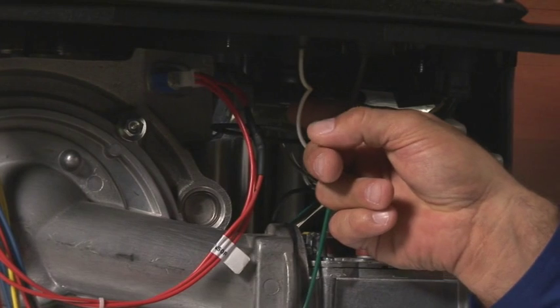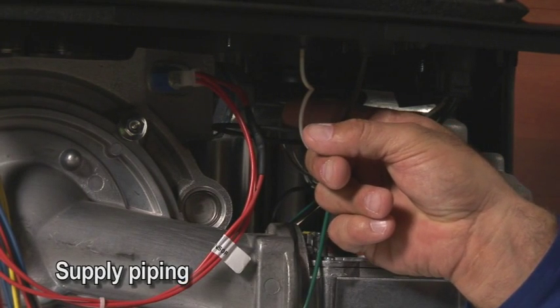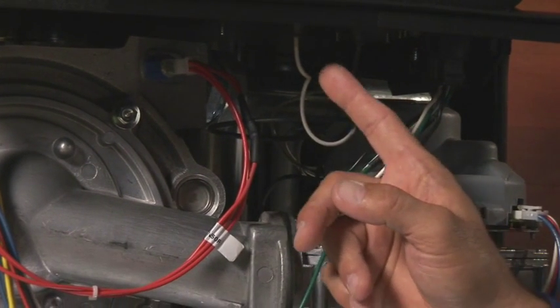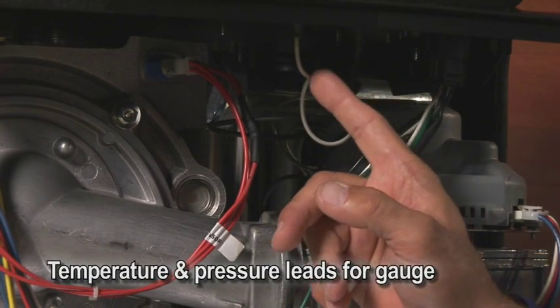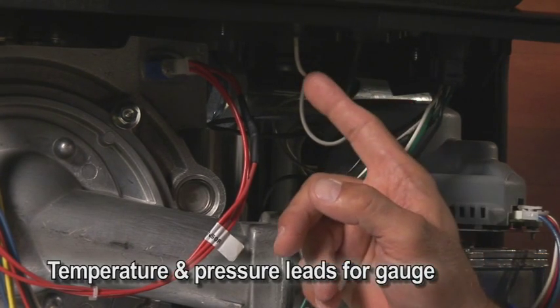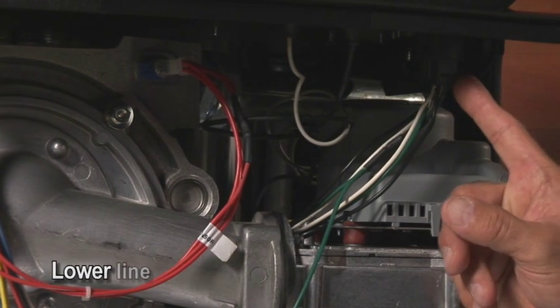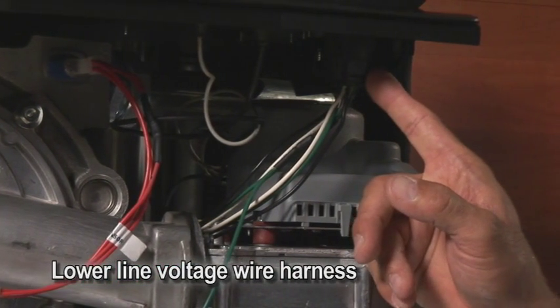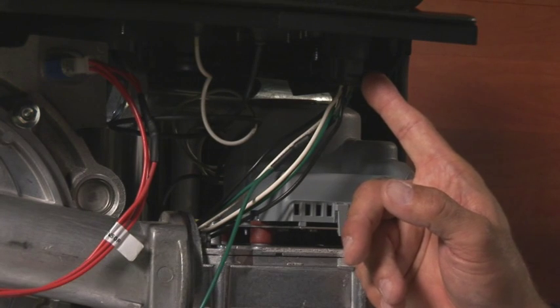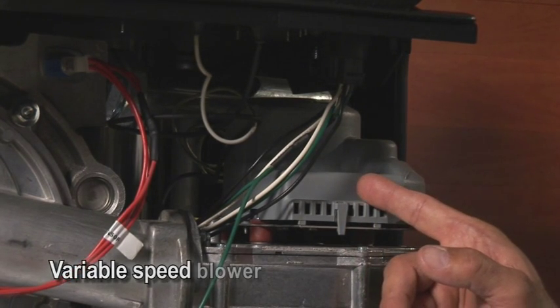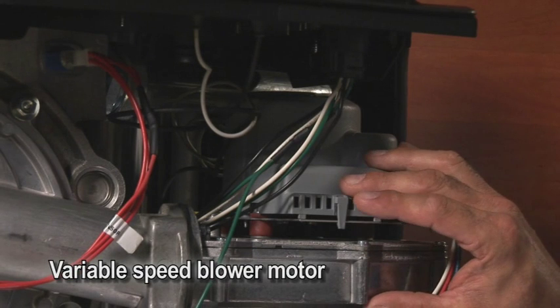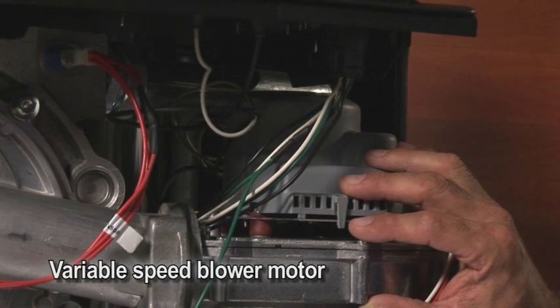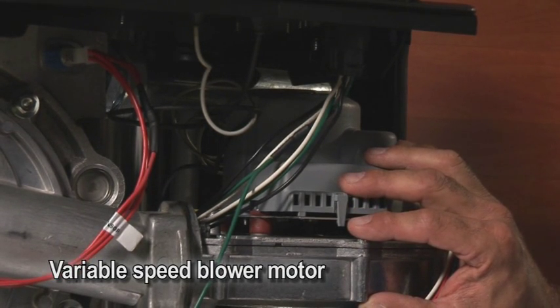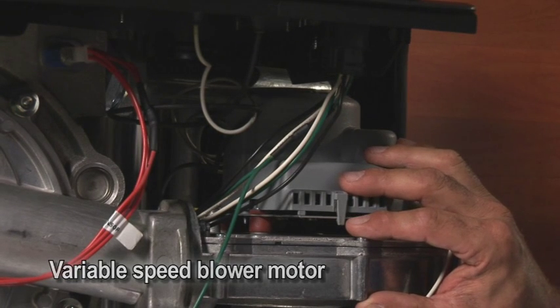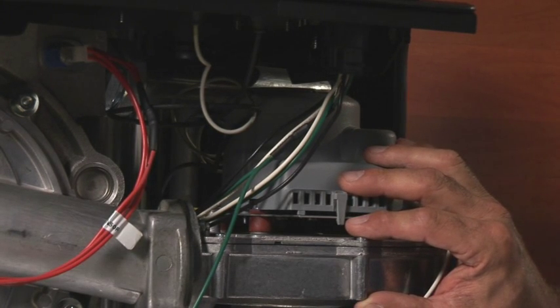Right next to that is the supply piping, leaving the top portion of the heat exchanger. Here we have the tridicator temperature and pressure cords. Here we have another plug-in connector. This is a 120 volt connection that comes down to energize the blower motor. This is a variable speed blower motor. We send an AC current to it. It's converted to a DC current so we can control the RPM of the blower motor. We can go from 20% input to 100% input on the boiler.